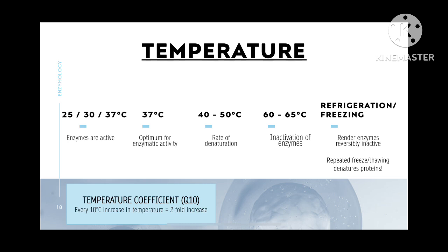Because of their temperature sensitivity, enzymes should be analyzed under strictly controlled temperature conditions. Incubation temperature should be accurate within plus or minus 0.1 degrees Celsius. Laboratories usually attempt to establish an analysis temperature for routine enzyme measurement of 25, 30, or 37 degrees Celsius. Attempts to establish a universal temperature for enzyme analysis have been unsuccessful, and therefore, the reference ranges for enzyme levels may vary significantly among laboratories.